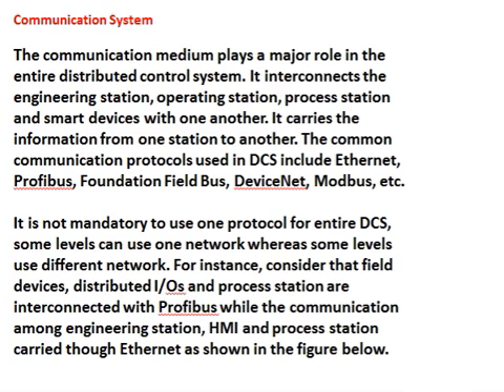It is not mandatory to use one protocol for the entire DCS. Some levels can use one network, whereas some levels use a different network. For instance, consider that field devices, distributed I/Os and process stations are interconnected with Profibus, while the communication among the engineering station, HMI and process station is carried through Ethernet, as shown in the figure below.